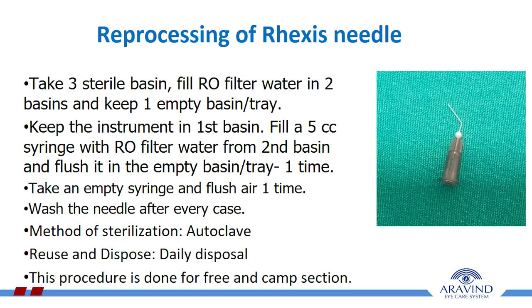Now we will see the reprocessing of Rhexis needle. Take 3 sterile basins, fill RO water in 2 basins and keep 1 empty basin or tray. Keep the instrument in first basin. Fill a 5 cc syringe with RO filter water from second basin and flush it in the empty basin or tray 1 time. Take an empty syringe and flush air 1 time. Wash the needle after every case. Method of sterilization is autoclave. There is daily disposal for this Rhexis needle, and this procedure is done for free and camp section.